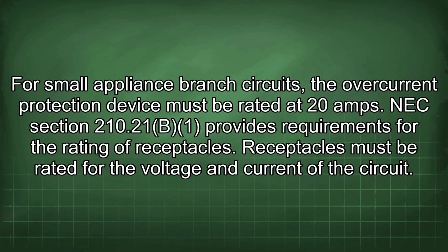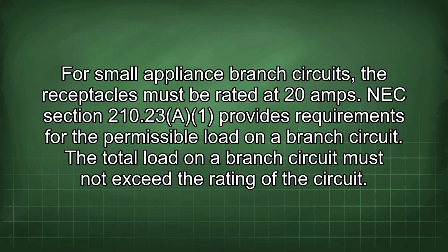NEC section 210.21 provides requirements for the rating of receptacles. Receptacles must be rated for the voltage and current of the circuit. For small appliance branch circuits, the receptacles must be rated at 20 amps.